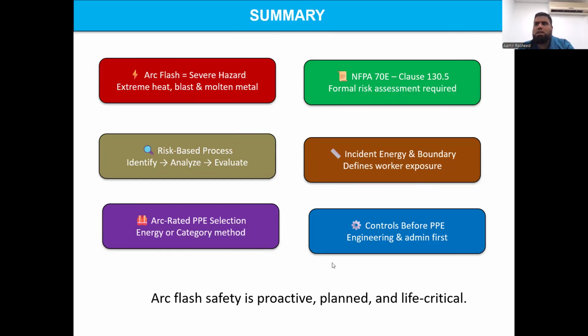Incident energy must be determined to define the worker exposure. Accordingly, the right PPE must be selected using the incident energy or PPE category method. Engineering controls, administrative controls like safe work practices, training, competency of the people, and proper labeling must be applied before relying on PPE, because remember, PPE is the last line of defense. One thing you need to make sure you understand: arc flash safety is proactive, planned, and life critical. That's my message in the end.